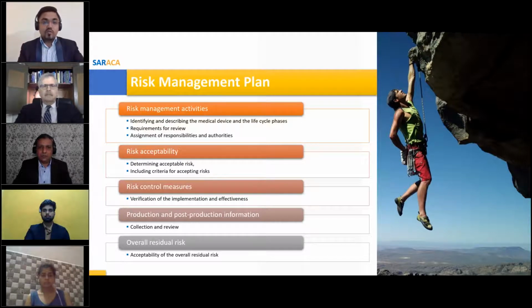Then overall residual risk. Once you finalize your overall residual risk, you need criteria for what type of overall residual risk you are going to accept and what type you are not going to accept. So at that time you need to define the criteria. What are the criteria you are following to accept the overall residual risk? Those criteria also need to be defined: the acceptability, how you are going to accept the overall residual risk, and what process you are going to implement to evaluate it. So you need to define all those requirements in this risk management plan.